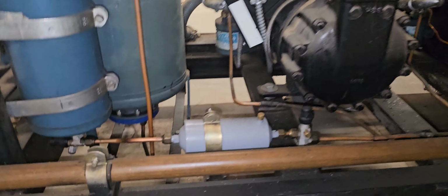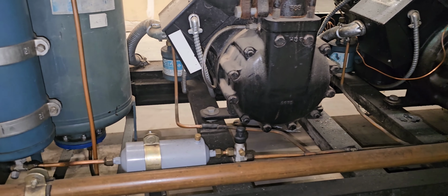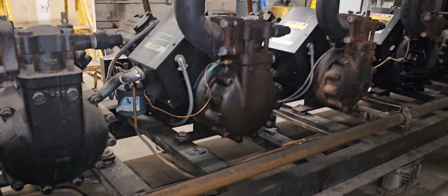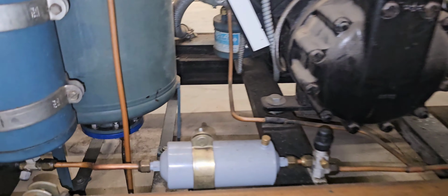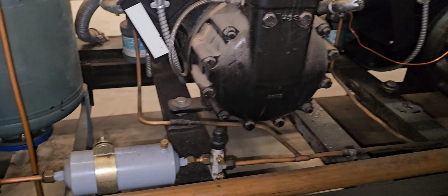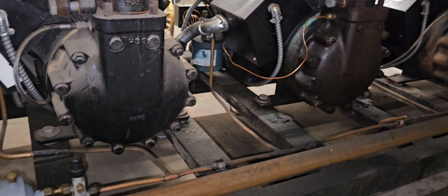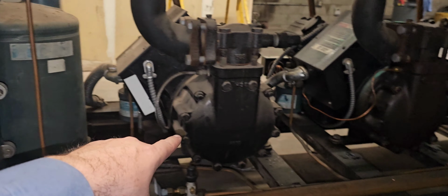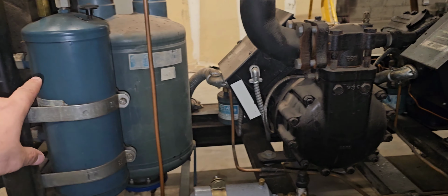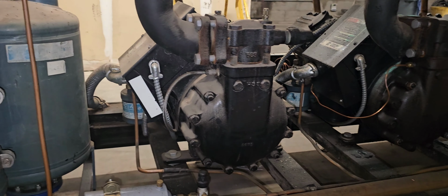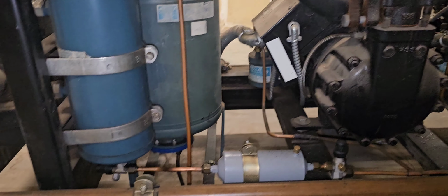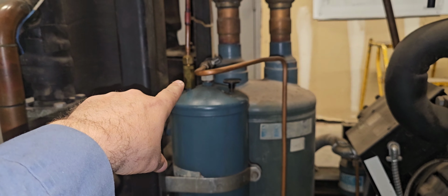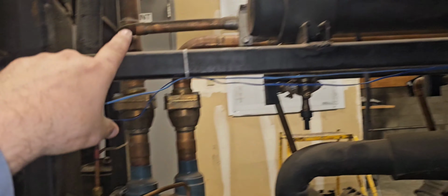Just like all of refrigeration, you need that differential of pressure in order to move oil, in order to move refrigerant. It doesn't matter what it is, you can't have the same pressure and expect to move whatever you're trying to move. So we make this a little bit higher pressure than our crankcase pressure, but not too much to where it's blowing out that oil. So instead of having that Y valve, that oil differential valve, we have that OCV, or oil check valve, that's going to check that pressure off.